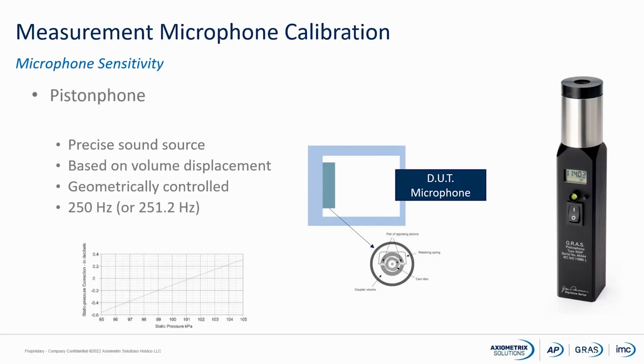And for the frequency of 250 Hertz, many piston phones are calibrated very, very precisely to give a frequency of 251.2 Hertz. That's due to it being the real center frequency of a 1/3 octave filter. It also has a very precise level. Many piston phones give 114 dB, which is equal to 10 Pascal.